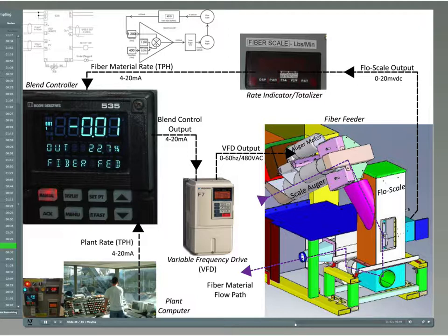Analog output, blend control output to control VFD speed. Digital output 1. Alarm relay on to illuminate deviation light when flow scale reading is significantly different than required set point.